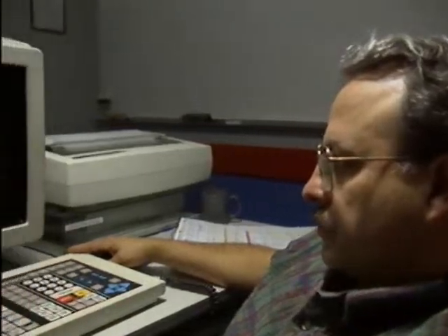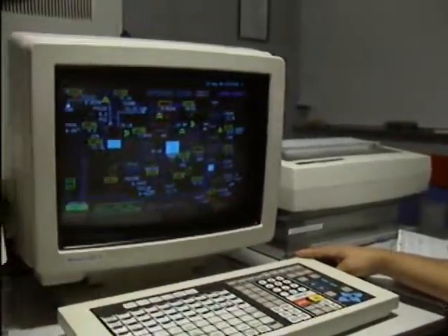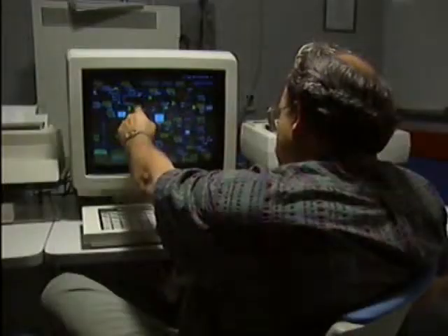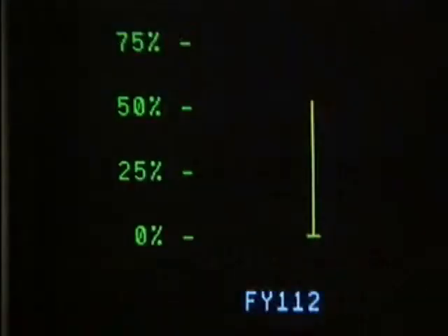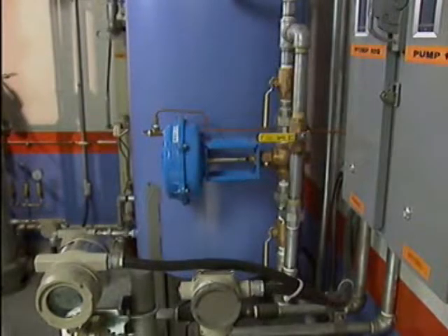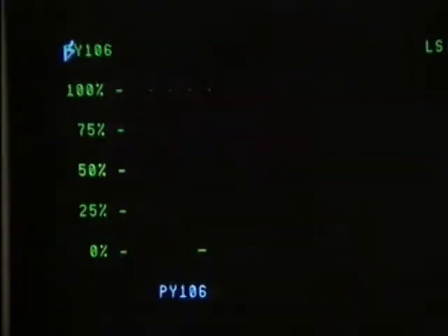At this point, the operators have eliminated most of the components in the process. Next, the operators check the positions of the control valves. First, they check the valve that controls flow to the collecting tank. They find that the valve is 50% open, which is its desired position. The operators next check the position of the recirculation line control valve. The control system indicates that this valve is shut.